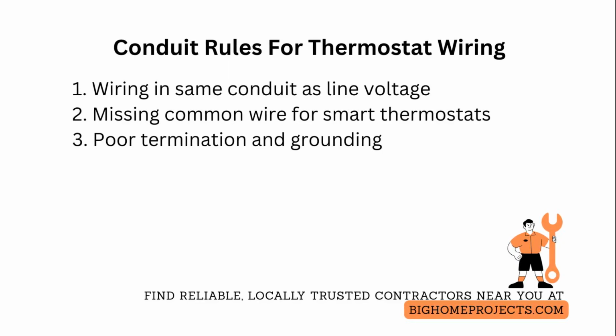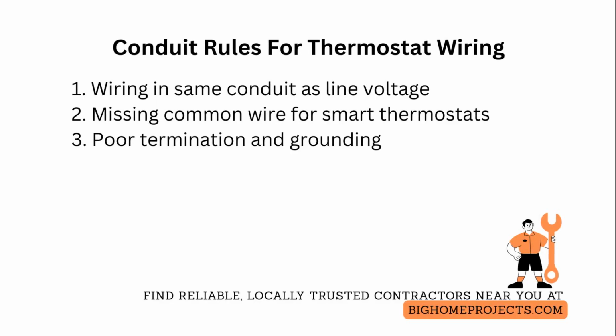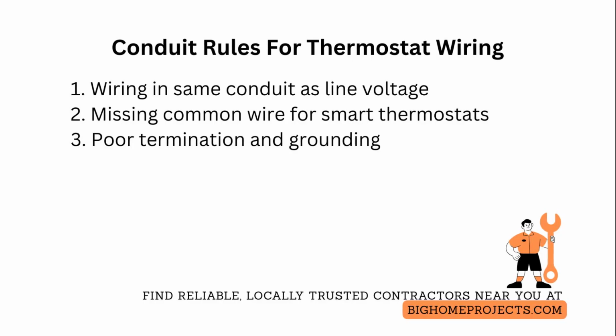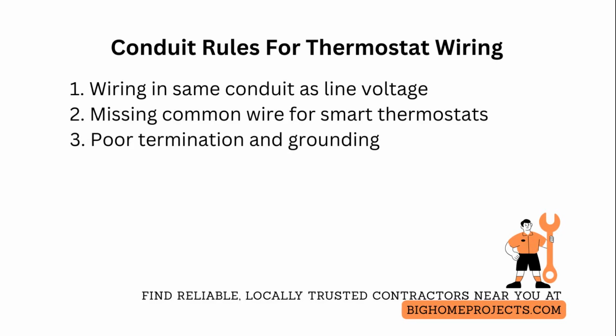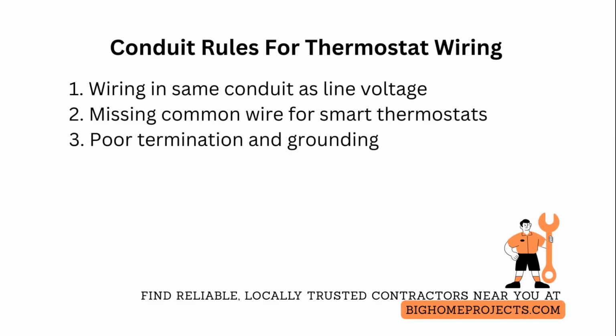Another common issue is not providing a common wire for smart thermostats, killing Wi-Fi connectivity and system performance. Resolve this by running a proper 5-wire cable with a dedicated common conductor back to the furnace, or installing a power extender kit from the thermostat maker.